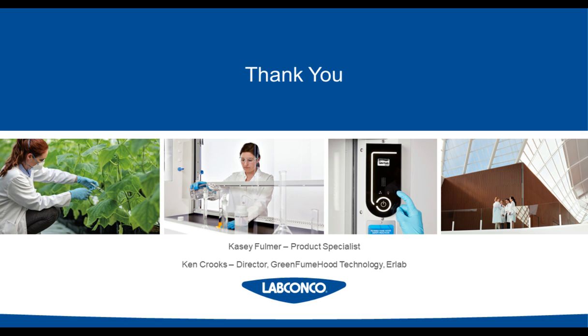Yep. To expand on this, these hoods, even without the baffle, have been put through a modified ASHRAE test. In that modified ASHRAE test, they use isopropyl alcohol and they still have very low detection limits, which is showing that the hoods are still containing even without the baffles.